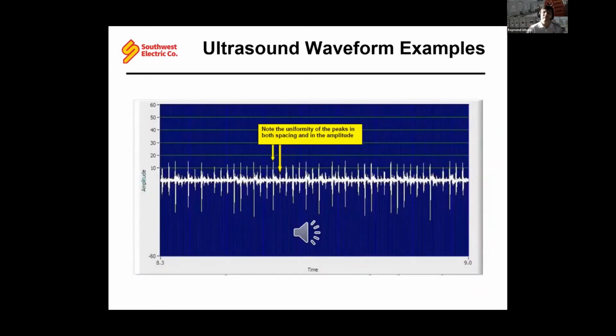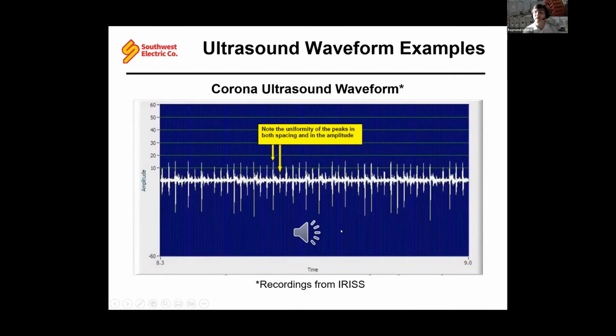We've got a couple of examples, and I'm not going to play these because they are kind of irritating to listen to, but the type of signature you see on your screen is corona. This is going to be your partial discharge, your breakdown within your insulation, and this is going to be the signature for it. So if your ultrasonic testing is detecting something within this signature and this kilohertz range, then you know it's going to be a partial discharge in that enclosure. Once you know that, you can start planning your outages to have a more detailed inspection of that insulation and replace as you need to.